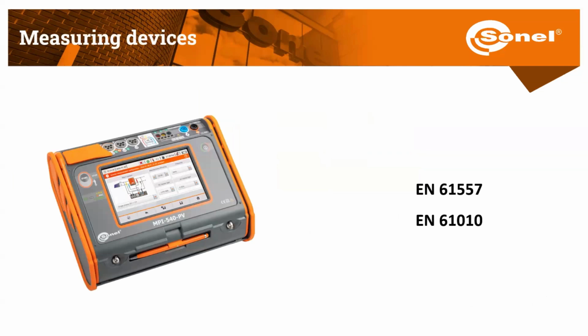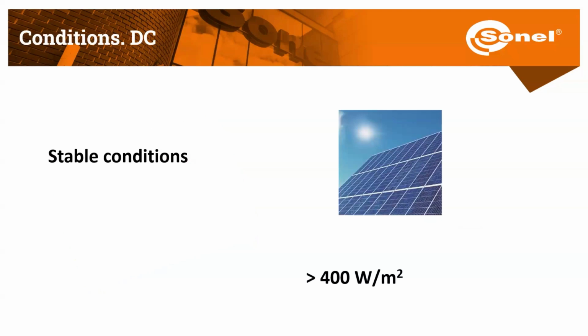Okay, to perform measurements, use devices that comply with the relevant parts of the IEC 61557 standard and have safety ensured according to the IEC 61010 standard. Measurements should be performed with a minimum irradiation of 400 watts per square meter. You can do the measurement if there is less than 400 watts per square meter, but if you want to recalculate the values to the standard condition, it will be harder. But you have to make the measurements under stable conditions.